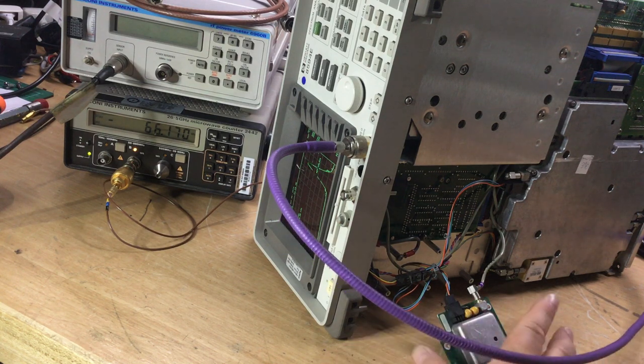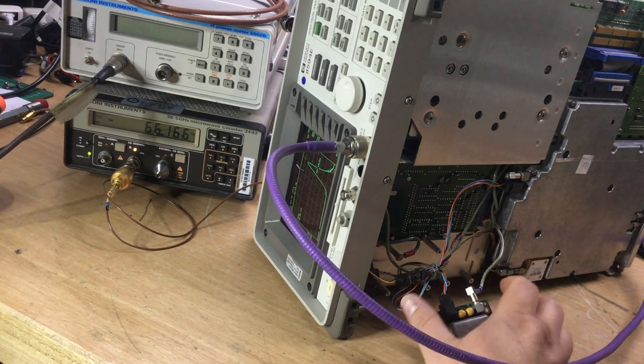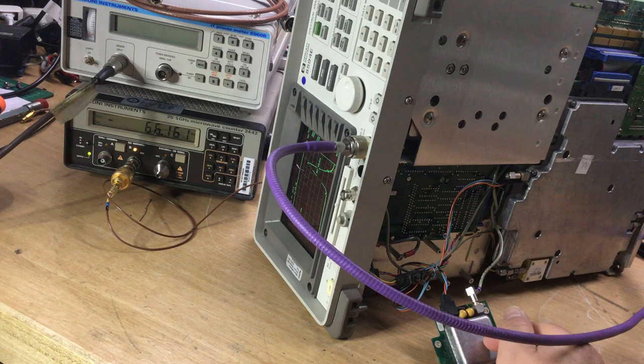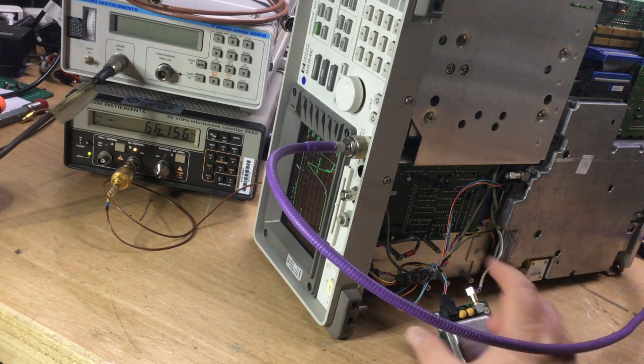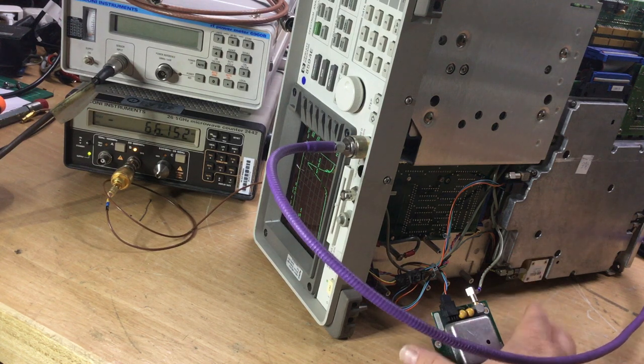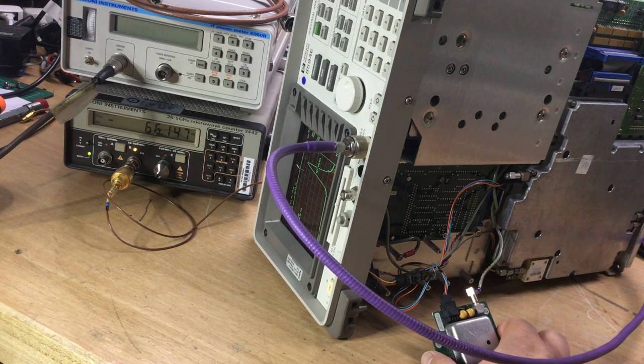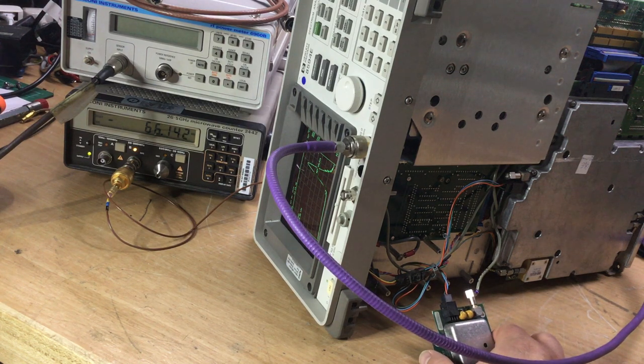So we have got a 10 megahertz signal coming out of this module. We know that to be correct because we measured that earlier. But the frequency here doesn't seem to be making any adjustment there. I thought it would do, making a coarse adjustment there, but it's not doing so. So it does look as if at this stage, and reading the service manual, the issue probably lay in the third converter 600 megahertz oscillator section. So we can have a look at that next anyway, see if we can get the board out and have a look at it, but we can't influence its frequency, and it should have locked, and it's not. So, interesting. We move onwards ever further.